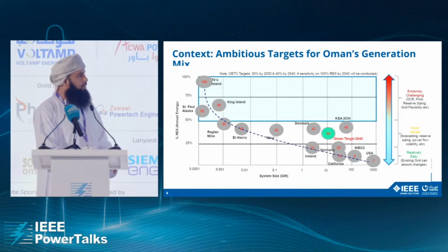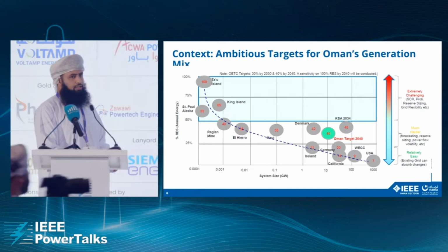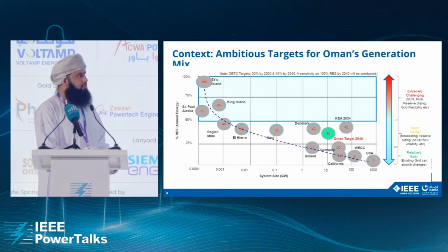As you know, we have three classifications of integration of renewable energy. If the renewable energy share is almost from 0 to 20% or 25%, the existing grids can cope with a small change and modification in the system. If we increase the renewable energy share up to 50%, there is a high change in terms of voltage support and frequency support to the system. Having more than 50% in the system will have a big impact on system stability, where a lot of changes should be made in terms of short circuit ratio, reserve for the system, and the stability margin of the system.